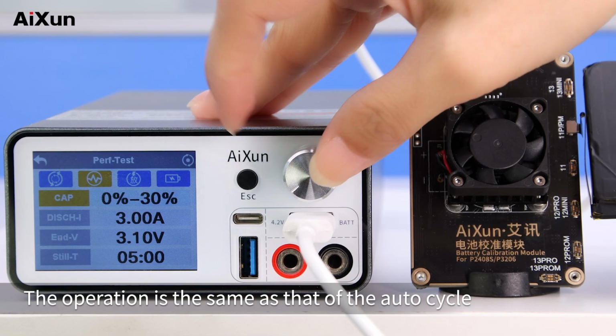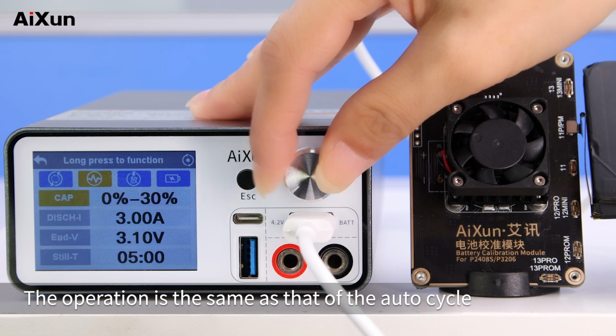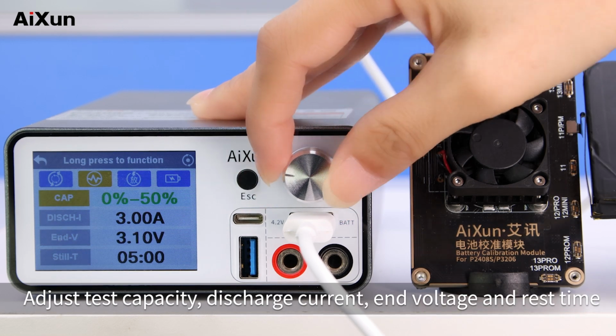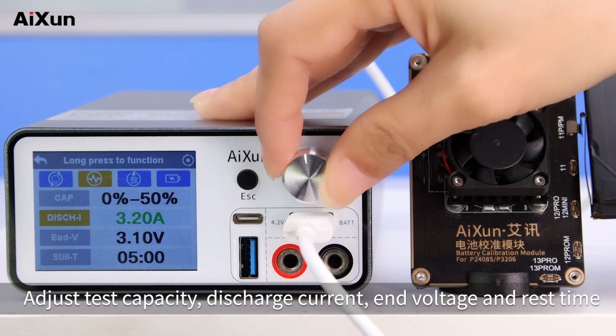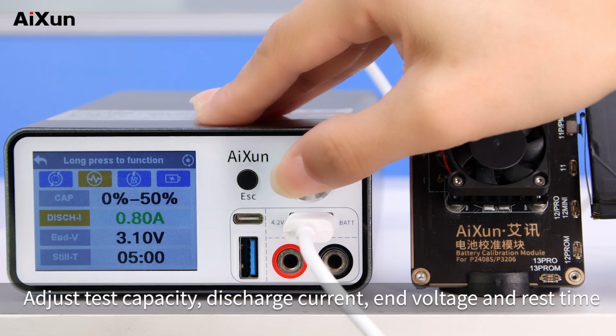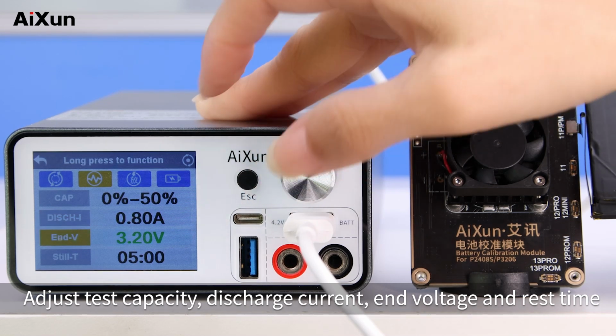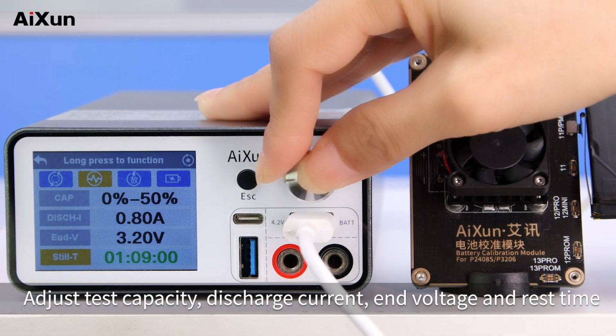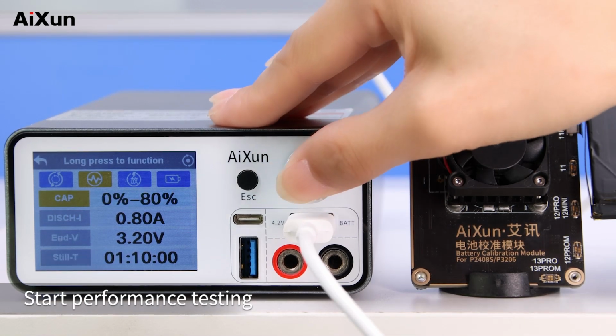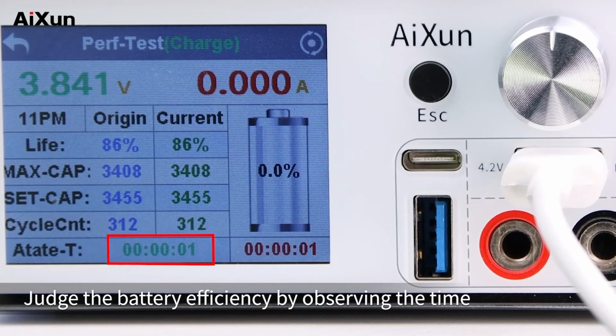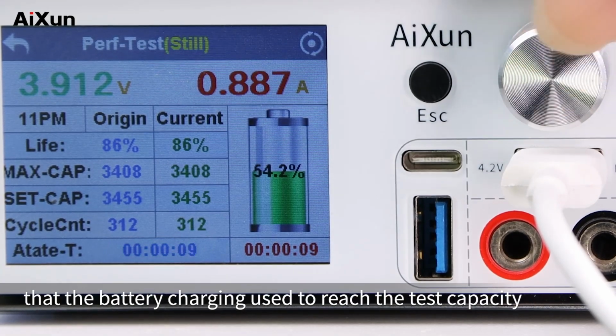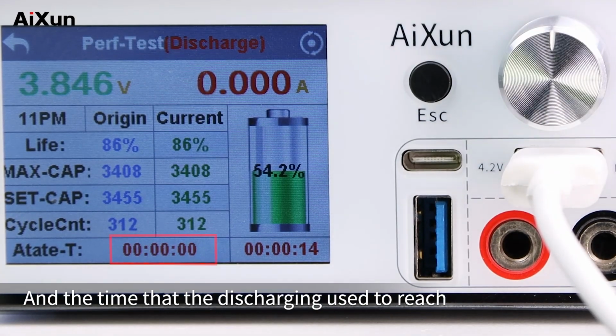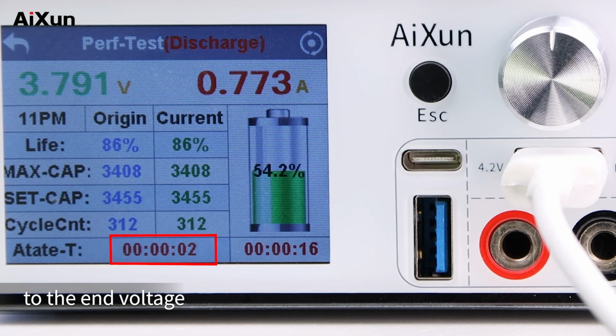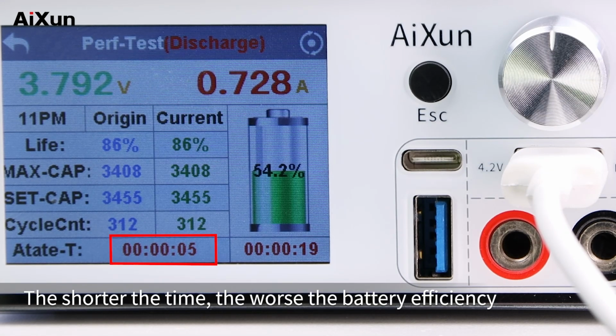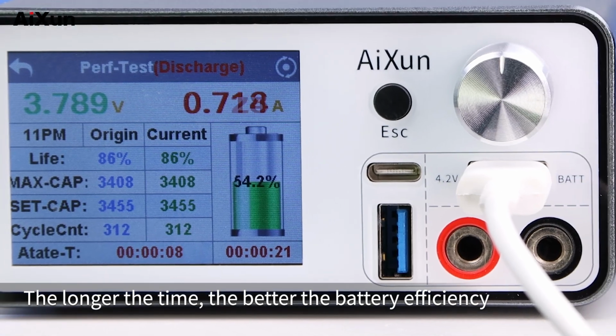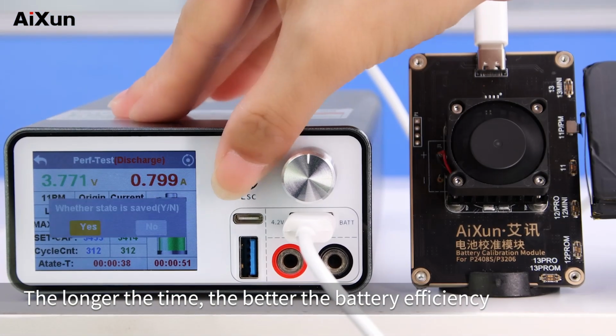Performance test. The operation is the same as that of the auto cycle. Adjust test capacity, discharge current, end voltage and rest time. Start performance testing. Judge the battery efficiency by observing the time that the battery charging used to reach the test capacity, and the time that the discharging used to reach the end voltage. The shorter the time, the worse the battery efficiency. The longer the time, the better the battery efficiency.